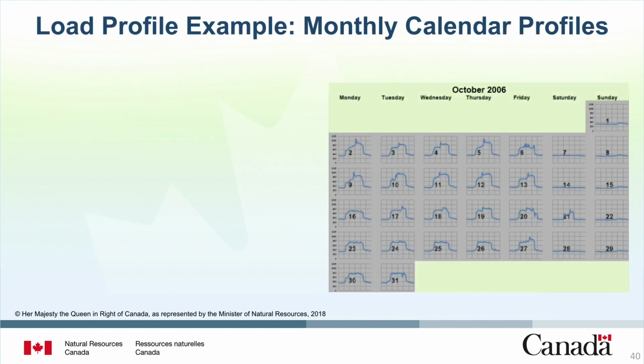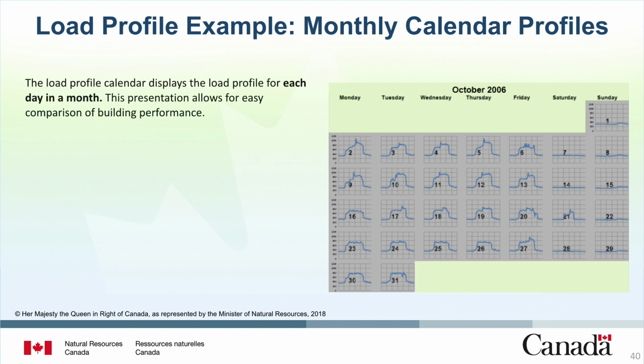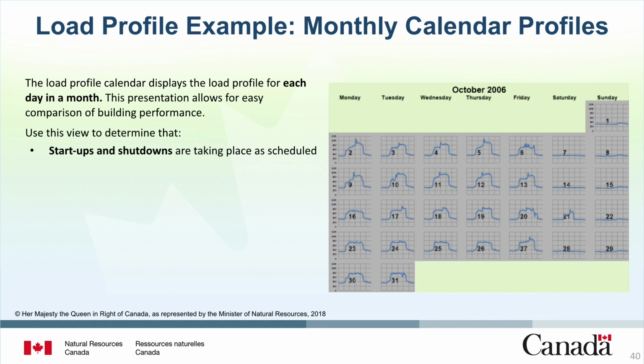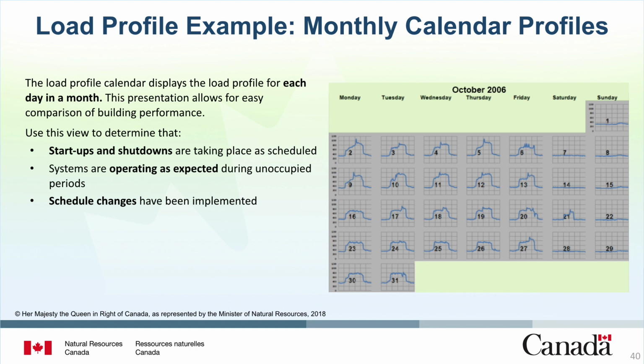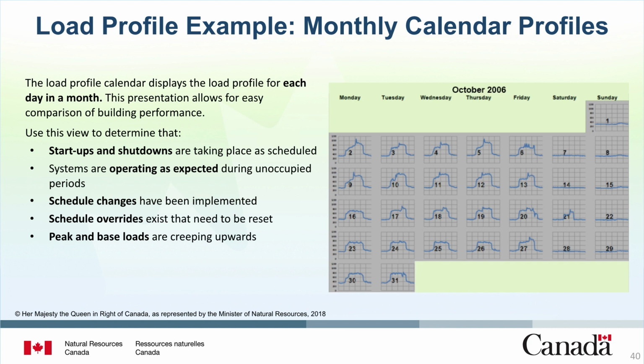Now let's look at a load profile for 1 month. This is a load profile calendar that displays the building load profile for each day in a month. This presentation allows the user to quickly check and compare building performance. A building operator can use this view to determine whether startups and shutdowns are taking place as scheduled, systems are operating as expected during unoccupied periods, schedule changes have been implemented, schedule overrides exist that need to be reset, and peak and base loads are creeping upwards. The load profile calendar is a good screening tool to identify points at which additional information is needed.